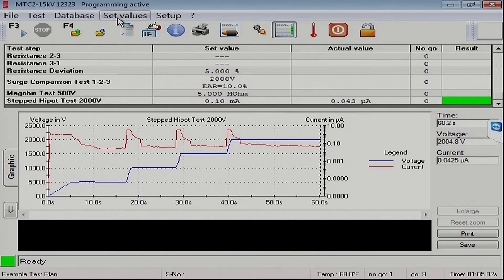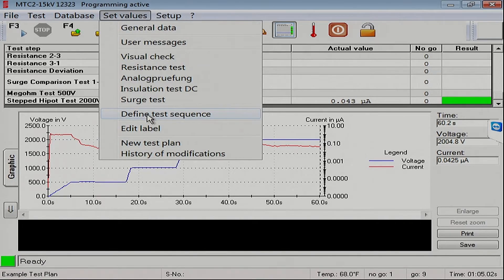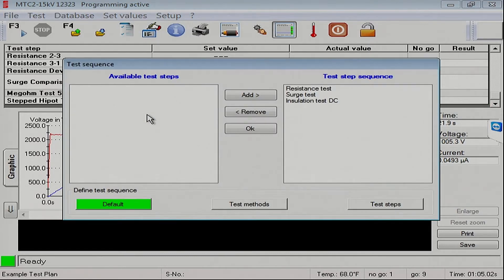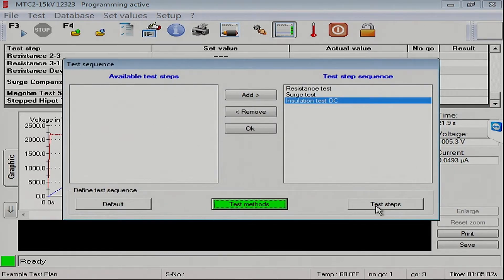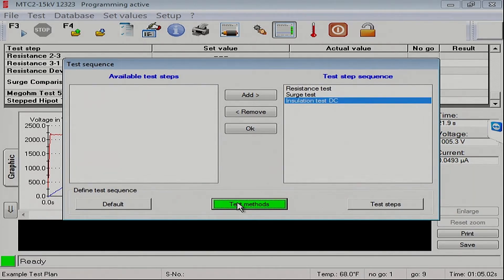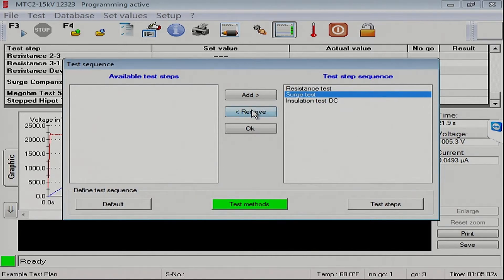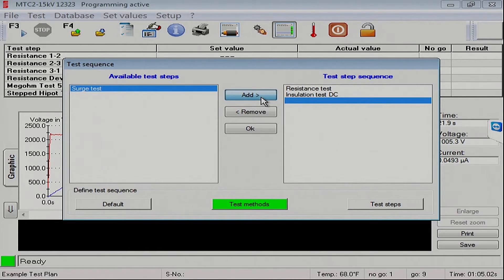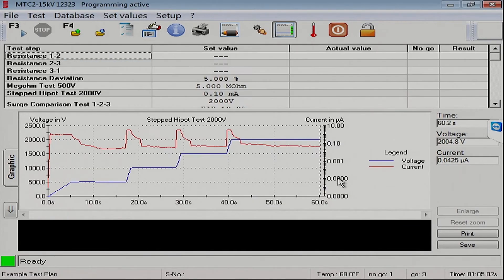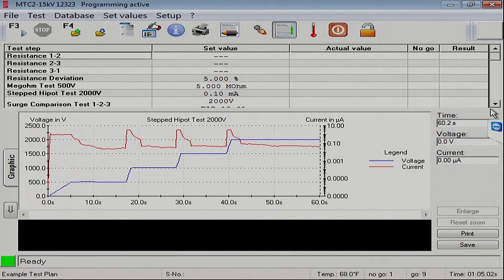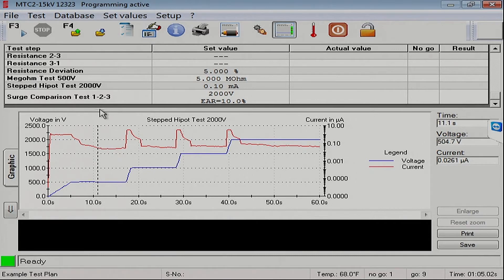What we will do to change the order is we'll come down here to that menu item called Define Test Sequence. Here, we've got test methods we can look at, as well as the individual test steps that we can mess with. Looking at the test methods, what I'm going to do is remove the surge test from the sequence, then add it back in at the bottom. And now we have what we're used to seeing here in the United States of resistance, megohm, and surge.